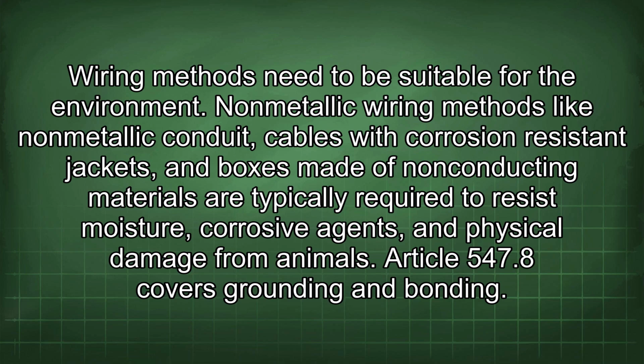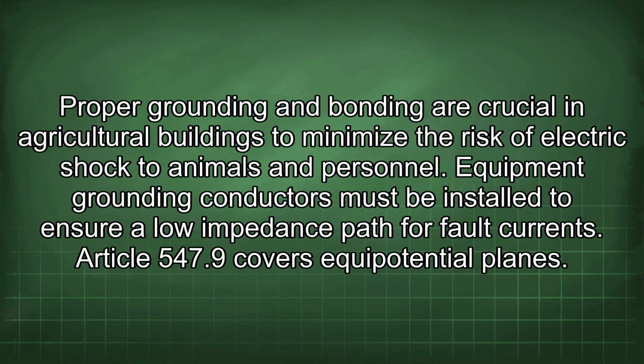Article 547.8 covers grounding and bonding. Proper grounding and bonding are crucial in agricultural buildings to minimize the risk of electric shock to animals and personnel. Equipment grounding conductors must be installed to ensure a low impedance path for fault currents.